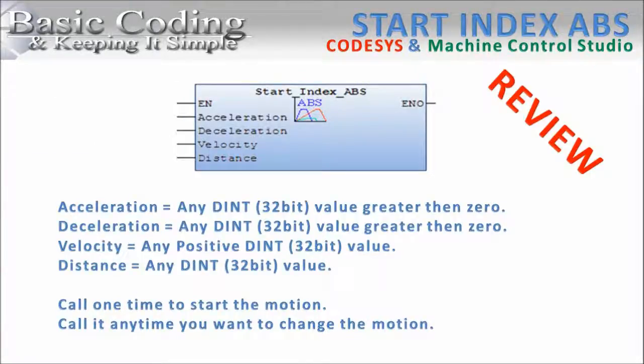Before we do the code example, I want to review the inputs to this block. All the inputs are 32-bit dint values. Acceleration and deceleration have to be values greater than zero. A value of zero will cause the drive to trip. The velocity must be a positive value, but can be zero. The distance command can be negative or positive. To use this block, we call it one time to start the index, or we call it any time we need to change the profile settings.